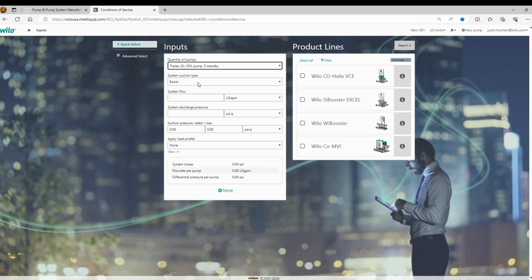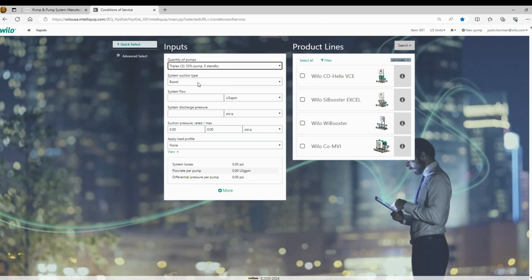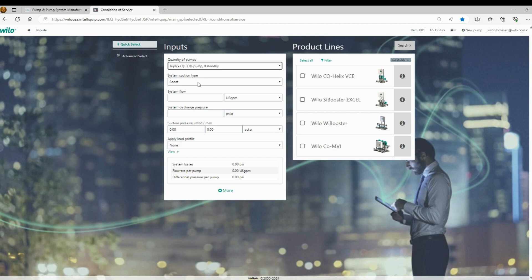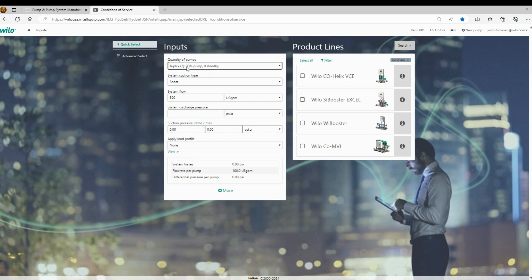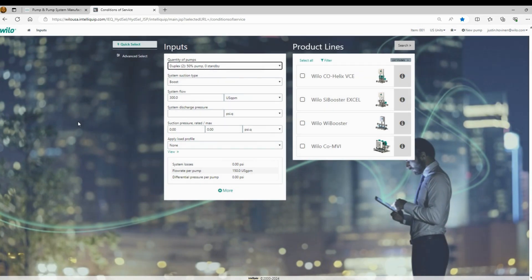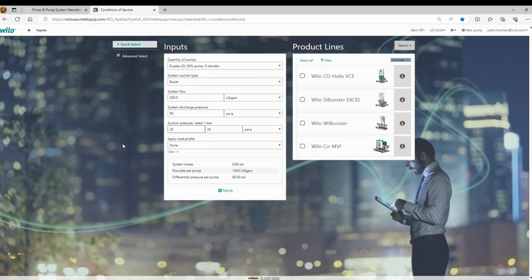There's system suction type. You're going to have an option for boost, which will have a city pressure coming in and it'll calculate your differential pressure. You'll have an option for flooded suction if you're pulling from a tank, possibly in a municipal application, and there'll also be an option for HVAC. So in this example, we'll do 300 gallons a minute. We'll do a boost application. We will do a duplex with 50% flow split. And we will set our discharge pressure set point at 80 PSI. And then we will set the suction pressure at 20 PSI.